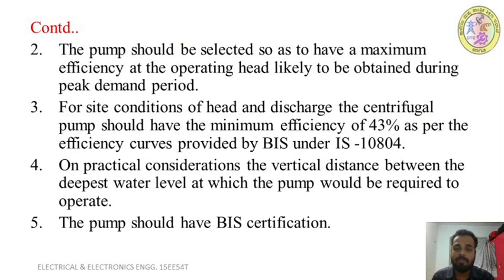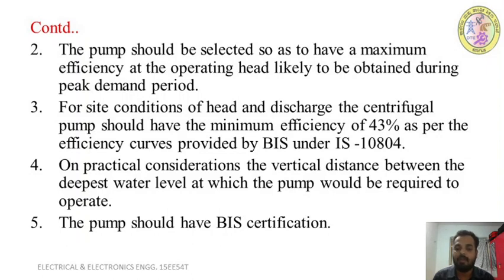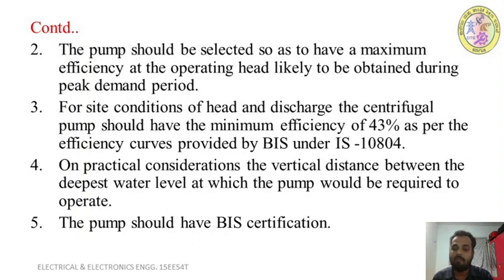The pump should be selected so as to have maximum efficiency at the operating head during the peak demand period. For site conditions of head and discharge, the centrifugal pump should have a minimum efficiency of 43%, as per the efficiency curves provided by BIS standards.